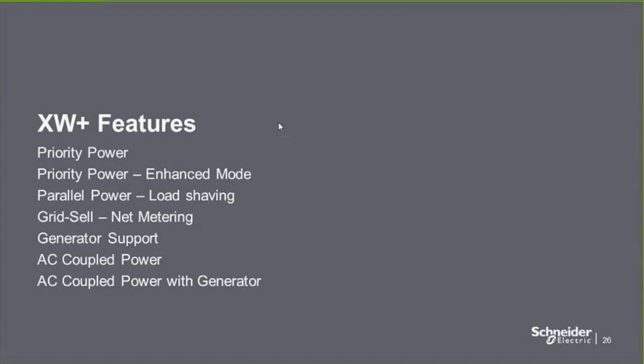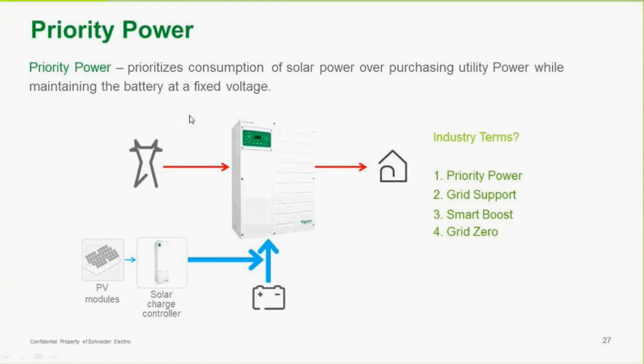So with those modes of operation, there are some features that are also attached. Priority power is also known by different names in the industry. What priority power does is prioritize consumption of solar energy over purchasing utility power. So what that means is, as long as you have PV production through a charge controller, that power is being used to support the loads.